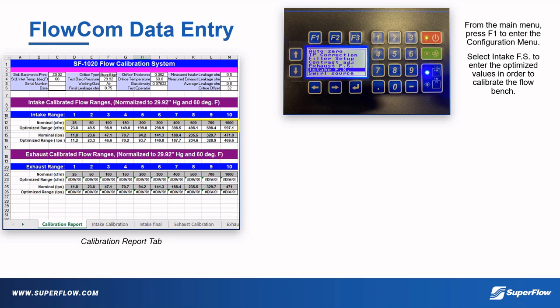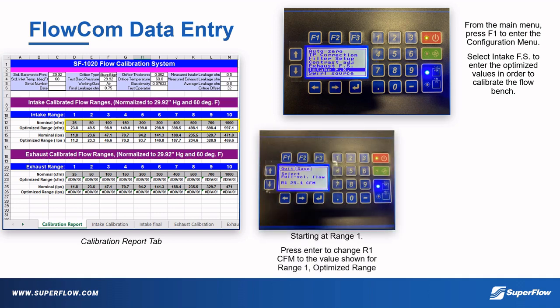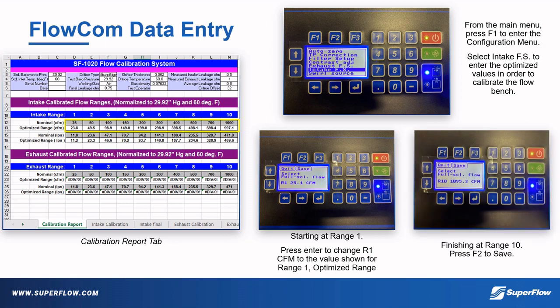On the FlowCom main menu, press F1 to enter into the configuration menu. Select Intake FS, or full scale, to enter these optimized numbers for the respective ranges. Starting at range 1, press Enter to change the CFM to the respective value shown for the optimized range on the table. Continue in this manner until you've completed all through range 10, and press F2 to save. This concludes the intake calibration.